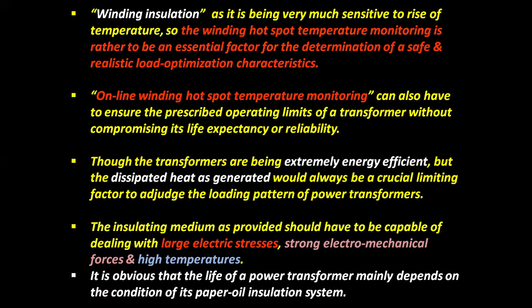Winding insulation is very sensitive to temperature rise, so winding hotspot temperature monitoring is an essential factor for determining safe and realistic load optimization characteristics. Online winding hotspot temperature monitoring can also ensure the prescribed operating limits of a transformer without compromising its life expectancy or reliability.